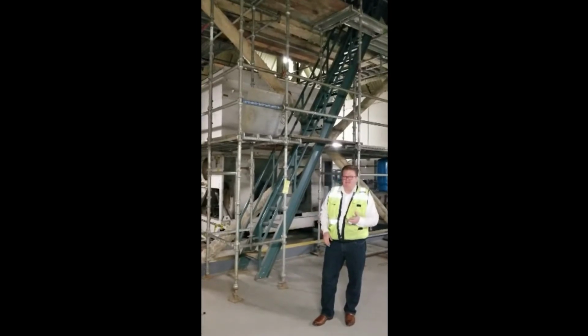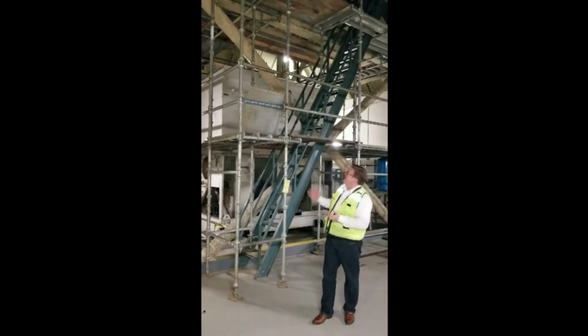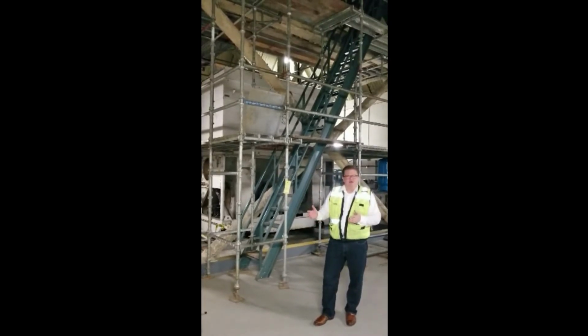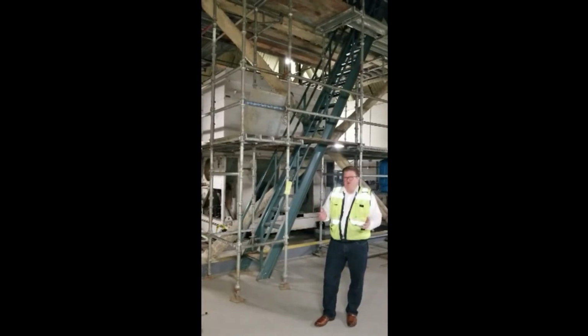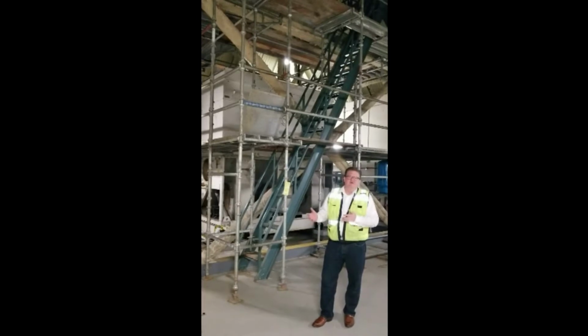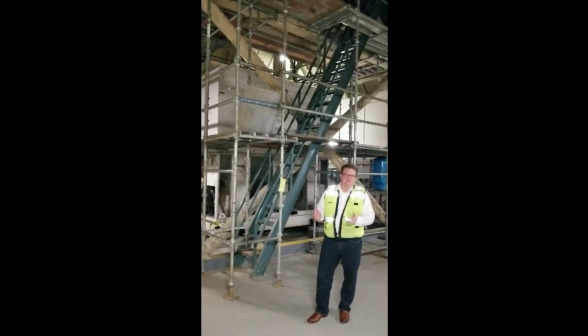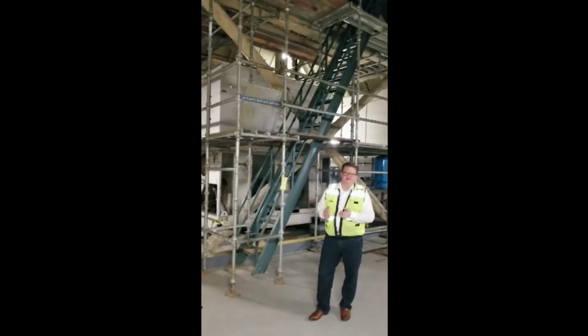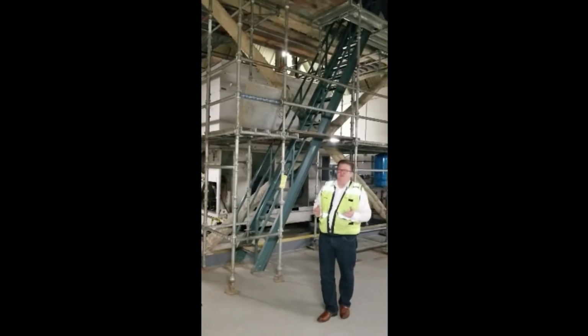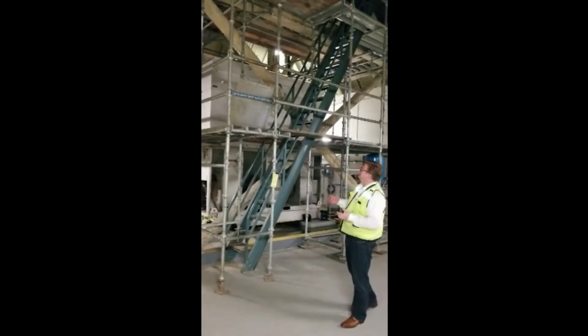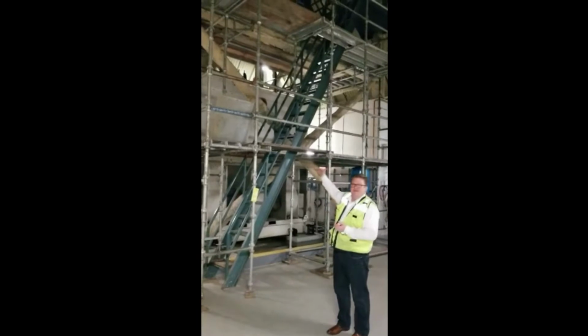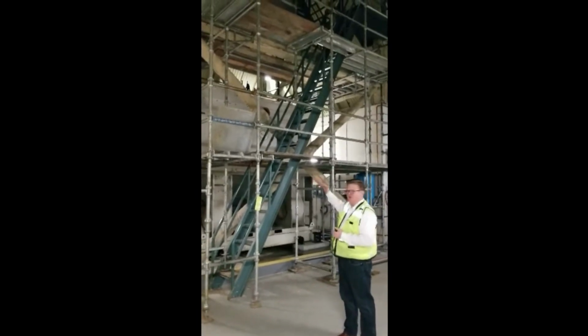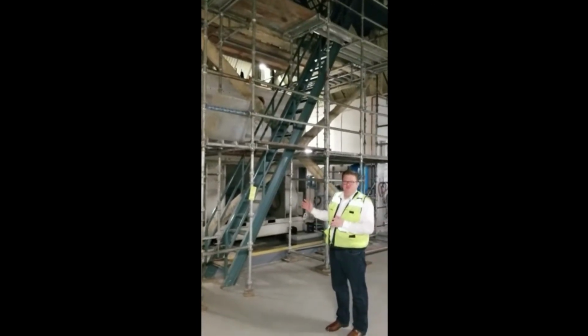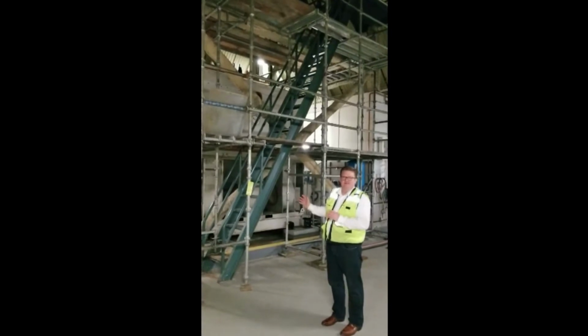In this case, we are looking at approximately a 30% upgrade by using new equipment. The new equipment will have 30 horsepower motors in lieu of the 40 horse motors that are in here currently. What you can see is we are hand demoing these towers, and we're going to hand build 2 new counterflow towers to take their place.